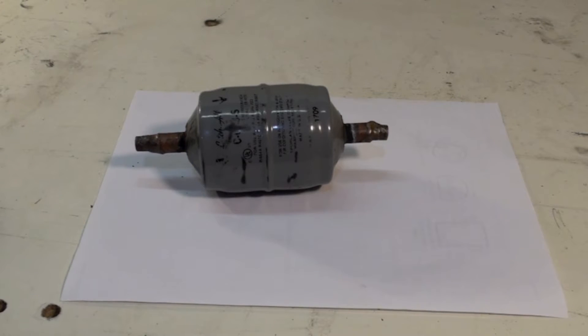This is just a short demonstration on what a liquid line filter dryer can occasionally gather. This filter dryer was removed from a running burnout compressor failure.